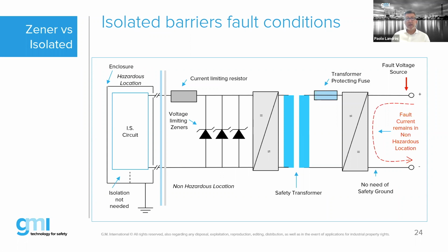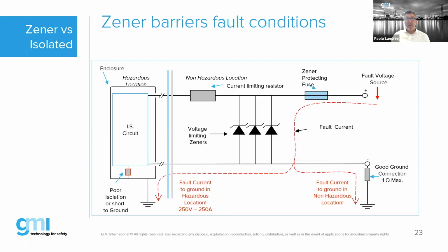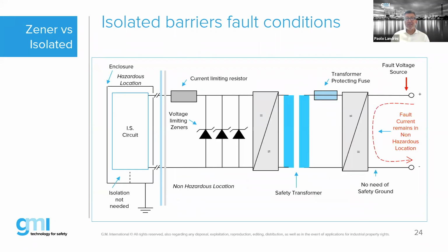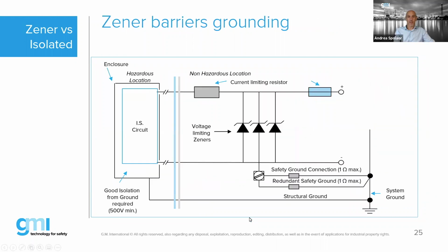A Zener barrier requires a safety ground, requires a ground connection. And the ground connection, as shown here, has to be unique, unipotential, dedicated, and by standard less than 1 ohm. Without this ground, the Zener barrier is floating and cannot divert a fault anywhere. In addition, as Andrea was saying, you need the isolation, because without isolation from ground, if you have more than 1 ground connection, then the fault can go to a different ground path, creating a problem. Sorry, I interrupted you, Andrea. Please continue.